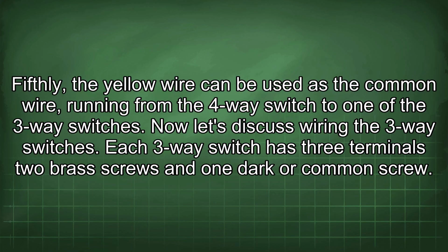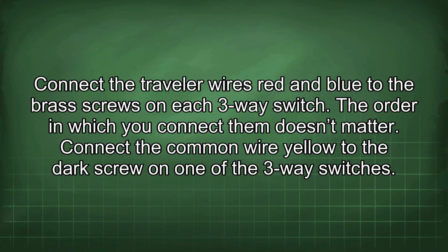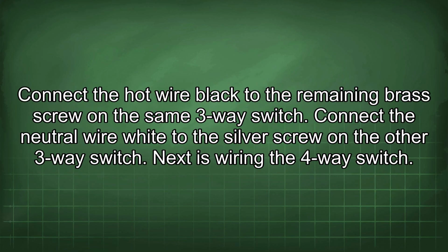Each 3-way switch has 3 terminals, 2 brass screws and 1 dark or common screw. Connect the Traveler wires red and blue to the brass screws on each 3-way switch. The order in which you connect them doesn't matter. Connect the common wire yellow to the dark screw on one of the 3-way switches. Connect the hot wire black to the remaining brass screw on the same 3-way switch. Connect the neutral wire white to the silver screw on the other 3-way switch.